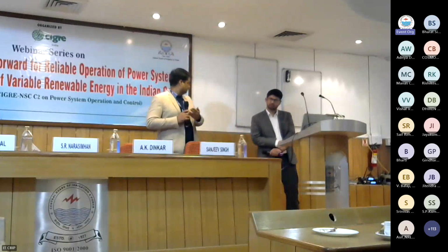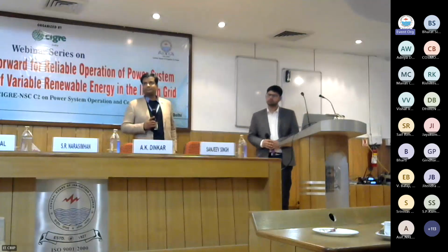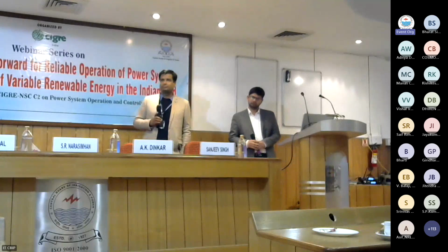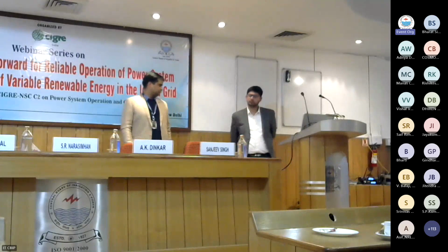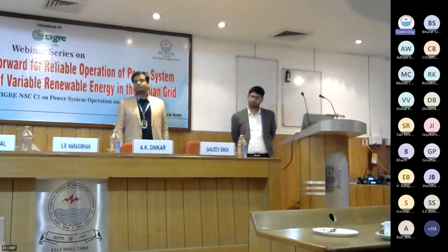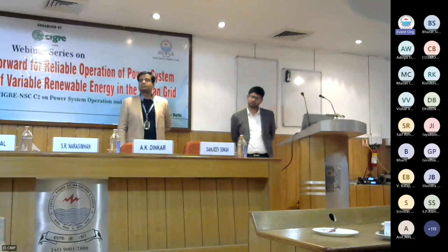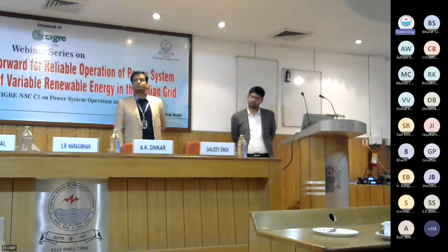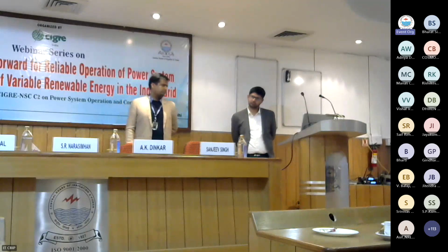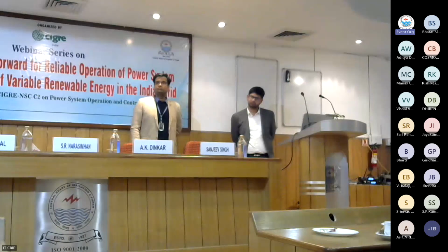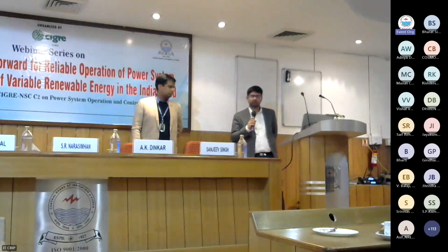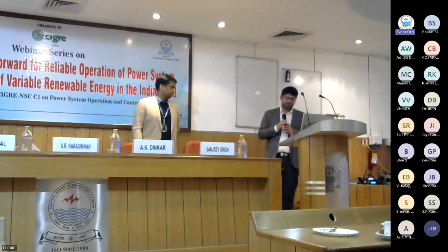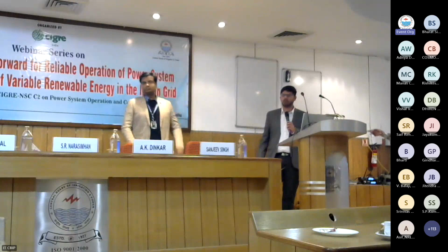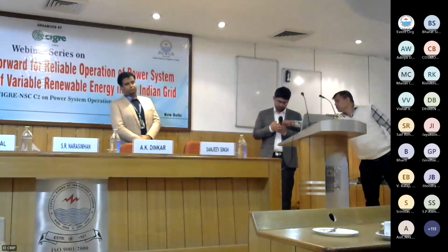I just wanted to ask that you have analyzed, there is a case of fault ride-through, and there is a case that there is a voltage surge whenever the reactor is getting open. Why are these events not analyzed with respect to unintentional isolation of the inverter or anti-islanding protection? Why are they not coordinated? Why is there no coordination between these two events while analyzing that? So it is not like there is no coordination or we are not analyzing these aspects also.